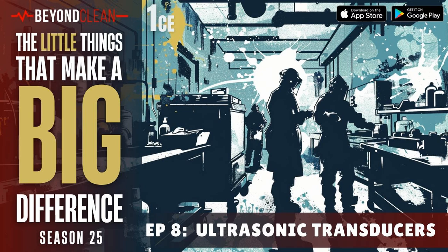Today, we're going to take a deeper dive into a technical topic: ultrasonic cleaner transducers, something that you probably haven't spent a lot of time thinking about in terms of making sure that your ultrasonic cleaner is working correctly. But similar to that conversation we had around the sterilizer door gasket, the transducer is one of those components of our ultrasonic cleaner that is crucial to make sure that it's functioning the way that it should be functioning. And it's unlike the sterilizer door gasket in that it's something that you usually can't see as a visual check to see if it's failing.